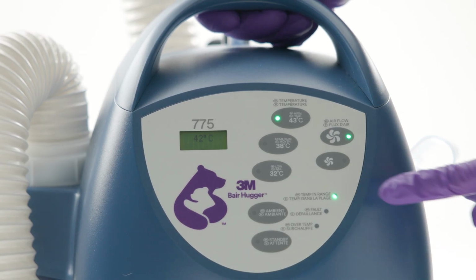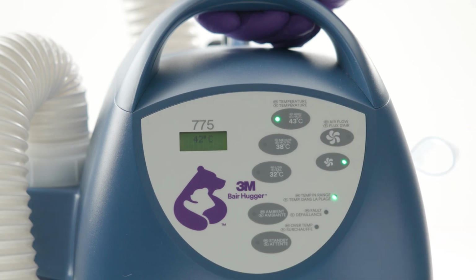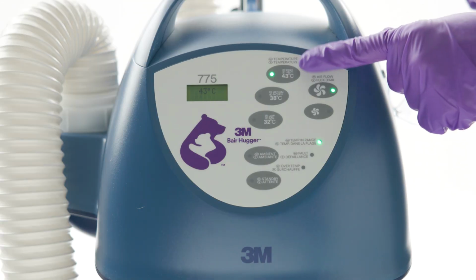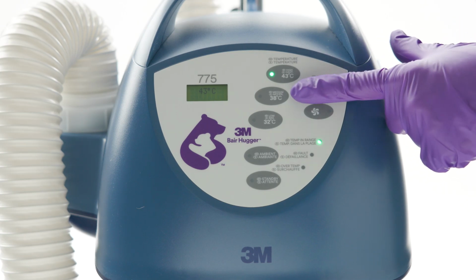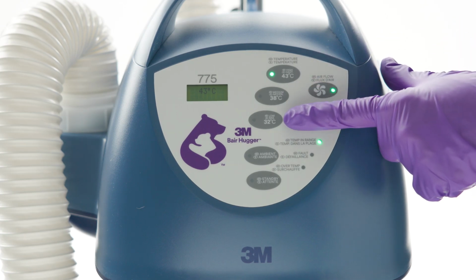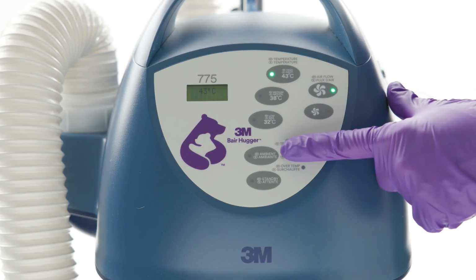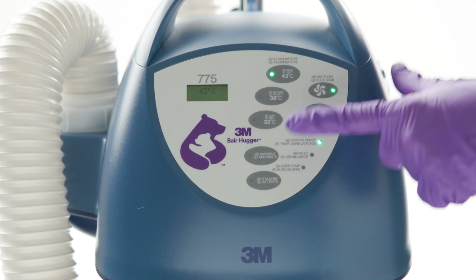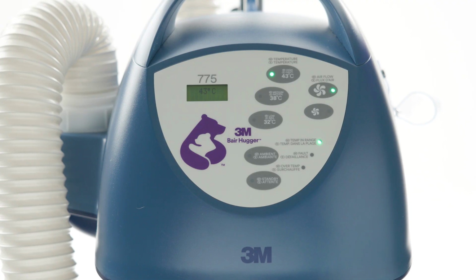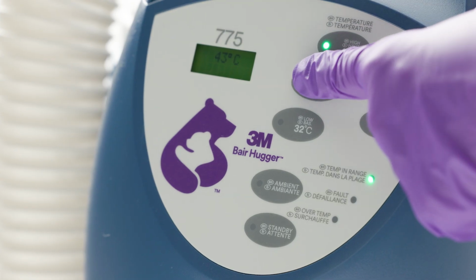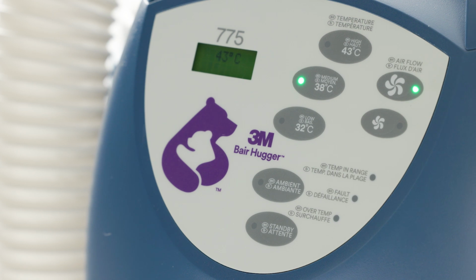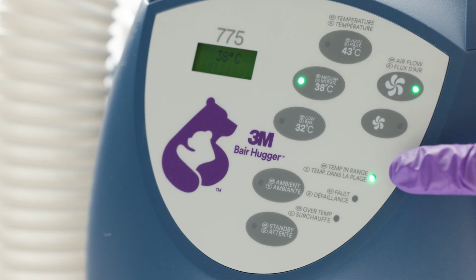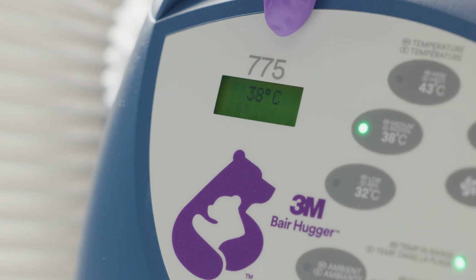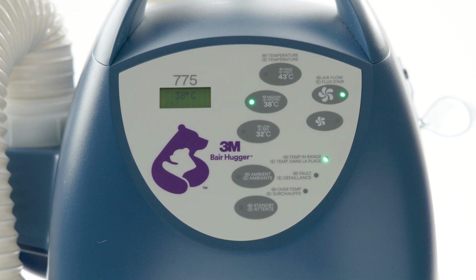At any time, the fan speed setting can be changed by pressing the corresponding button. There are 4 temperature settings: high at 43 degrees Celsius, medium at 38 degrees Celsius, low at 32 degrees Celsius, and ambient air, enabling the delivery of effective forced air warming as required by each individual patient. Select your required temperature. This will turn the unit and heater on. When the unit reaches the selected temperature, the Temp in Range button will illuminate, and the display screen will show the temperature at the end of the Bair Hugger warming hose in degrees Celsius. Ambient air setting will blow room temperature air.